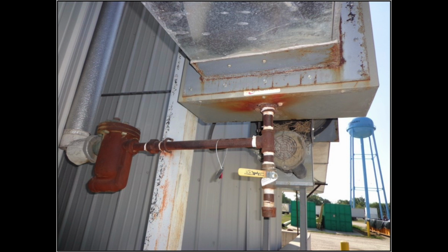If you decide to shut the unit heaters off during the summer months, then you want to shut the isolation valve, the steam isolation valve to the heater. You want to also have an option, as this picture here shows, of a valve of some sort between the outlet of the unit heater and the steam trap, so you can drain that unit heater. However, as you know, isolation valves don't always shut 100%. So that unit heater will fill up with condensate pretty quick. And therefore you have a unit heater that's full of condensate.